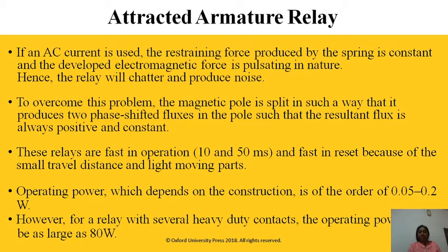Attracted armature relay: if an AC current is used, the restraining force produced by the spring is constant and the developed electromagnetic force is pulsating in nature. Why pulsating in nature? AC has a waveform like this, so definitely a positive half and a negative half, plus and minus. In the positive half, at a certain point it will actuate, and when the quantity goes in the negative direction, it will deactuate.